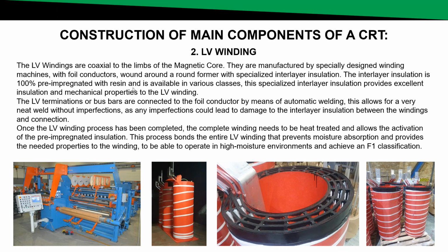By using this type of configuration for your LV winding, it also provides the LV winding with excellent insulation and mechanical properties. For the LV terminations or bus bars that need to be welded onto the actual foil of the LV winding, an automatic welding machine is used. This ensures that there are no imperfections or sharp edges on that weld, which could lead to interlayer insulation failure due to the stresses of the transformer during normal operations.